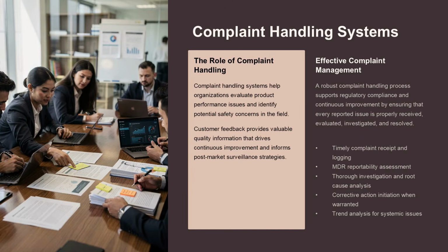Complaint handling systems help organizations evaluate product performance issues and identify potential safety concerns in the field. Customer feedback provides valuable quality information that drives continuous improvement and informs post-market surveillance strategies. An effective complaint handling process supports regulatory compliance and continuous improvement by ensuring that every reported issue is properly evaluated, investigated, and resolved. It involves timely complaint receipt and logging, MDR reportability assessment, thorough investigation and root cause analysis, corrective action initiation when warranted, and trend analysis for systemic issues.